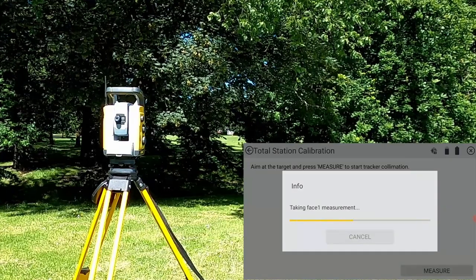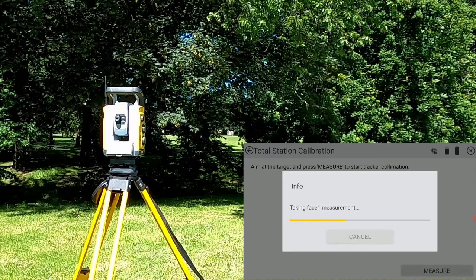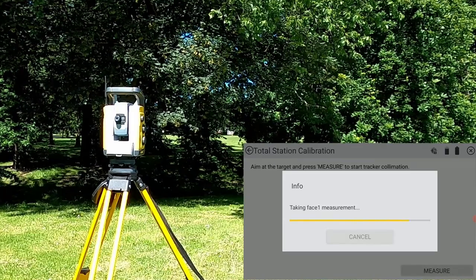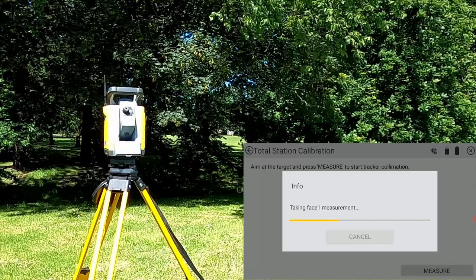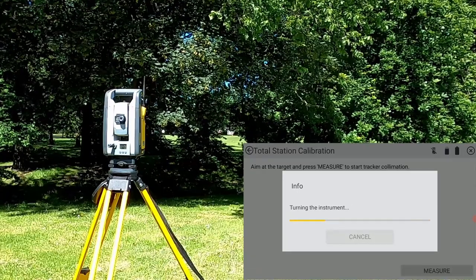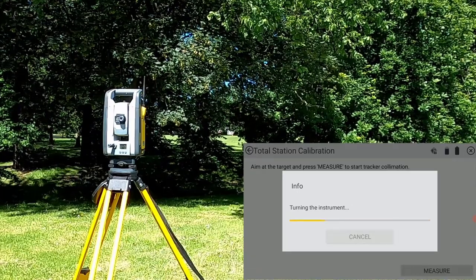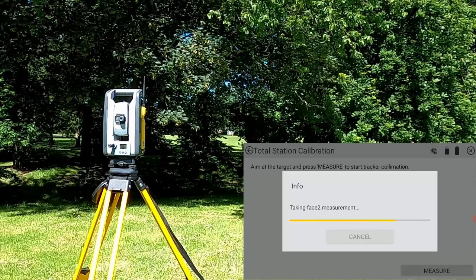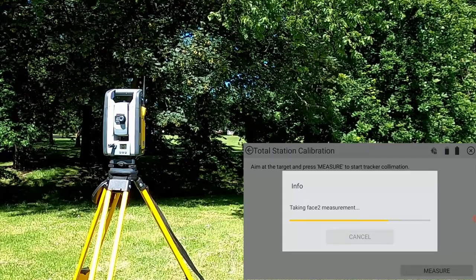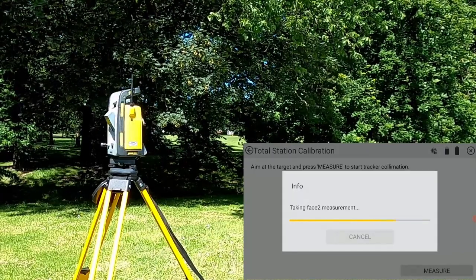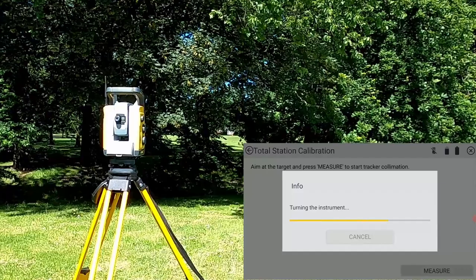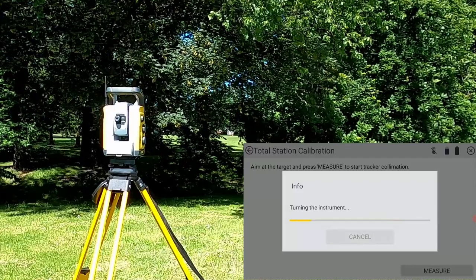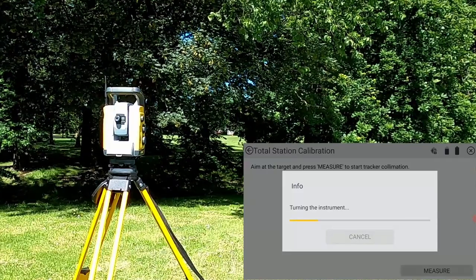After the first measurement, the instrument will automatically change face and take the face2 measurement. Once it's taken several measurements on face1 and face2, it will display the new and old values for the tracking collimation.